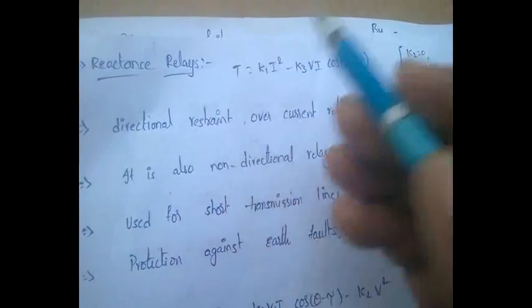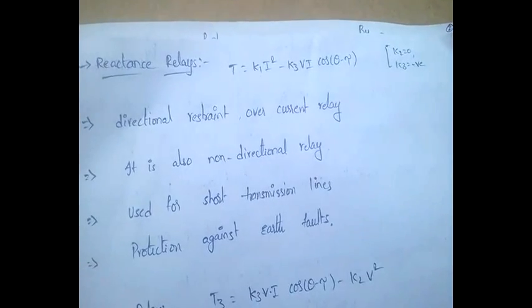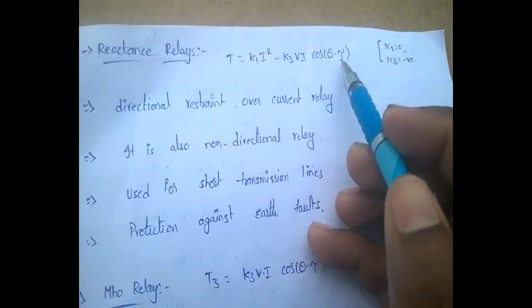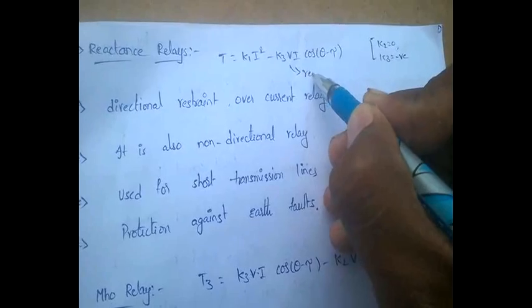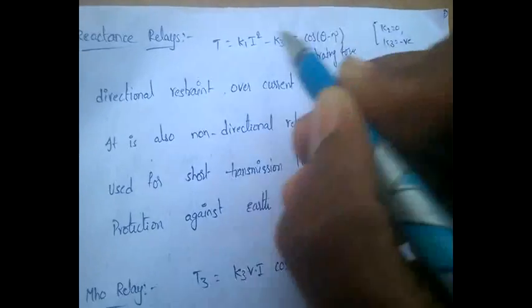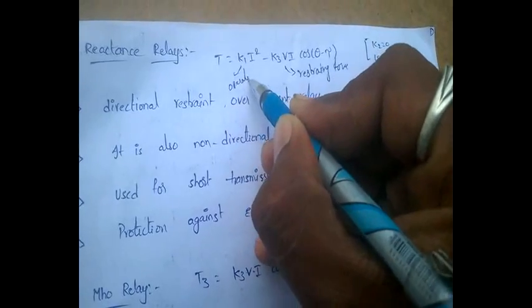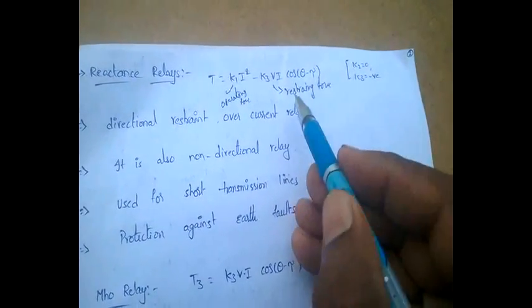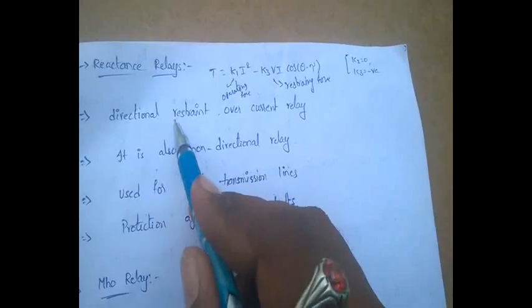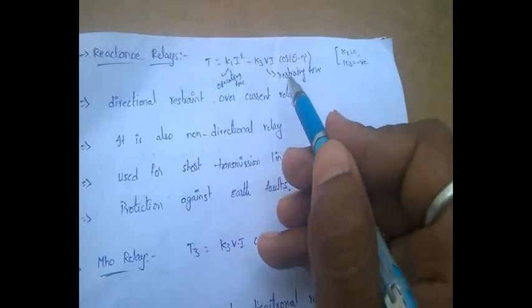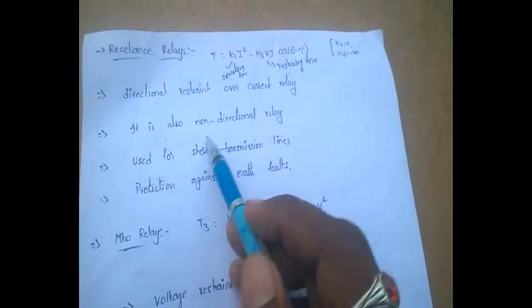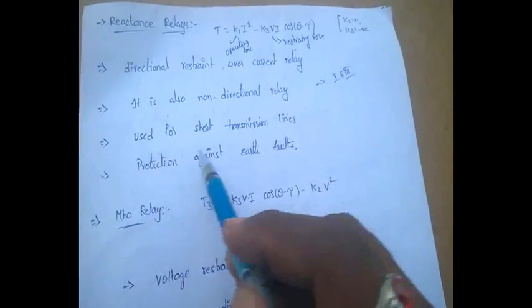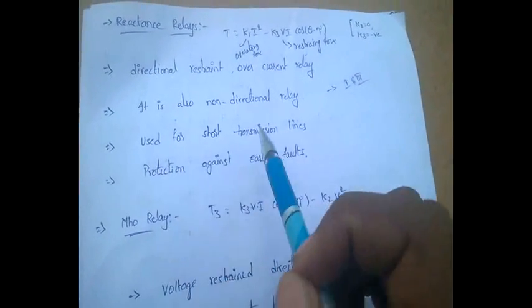For reactance relay, the torque equation is T = K1·I² − K3·V·I·cos(θ − τ). Here the restraining force is the directional part, and the operating force is current. So reactance relay is called a directional-restraint overcurrent relay. It is also a non-directional relay, operating in both first and third quadrants. Reactance relay is used for short transmission lines.